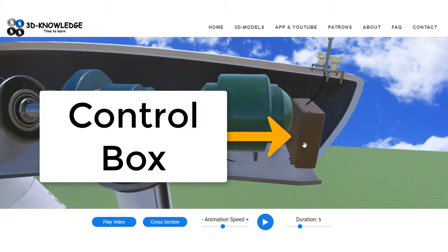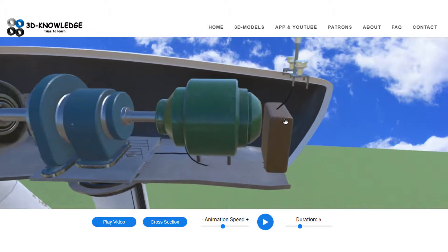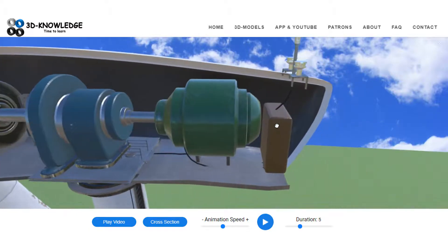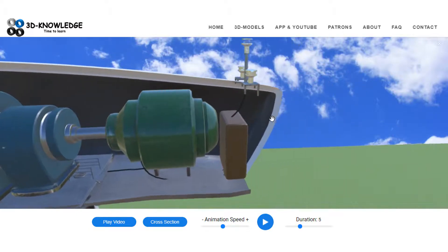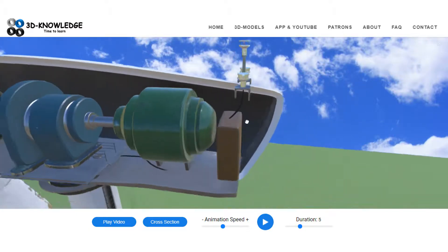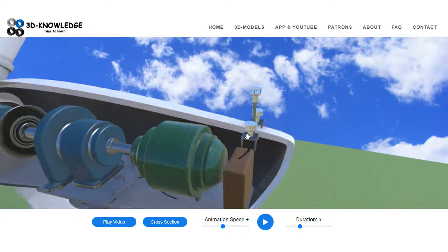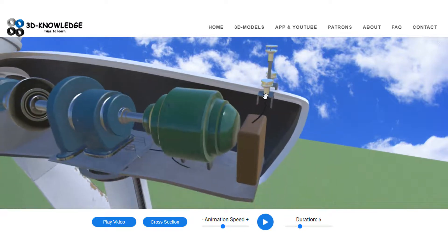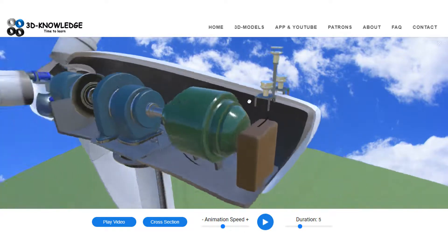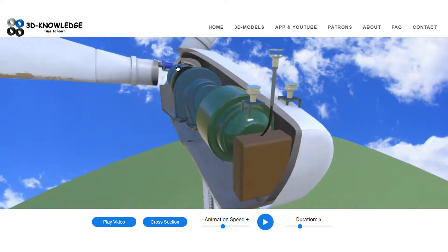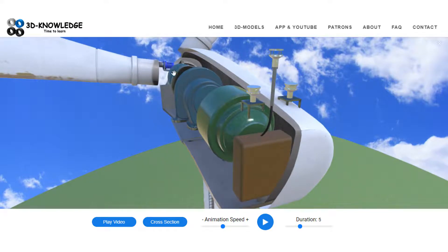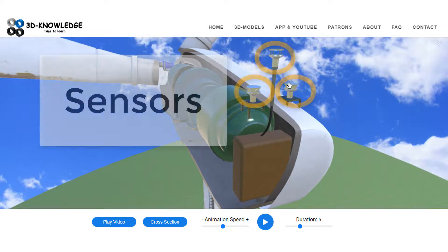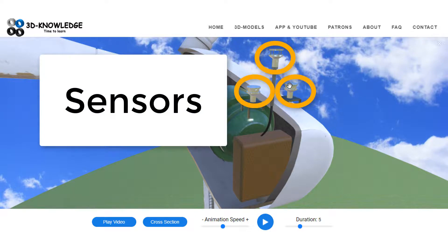We have a control box in the back—that's this brown item—and the control box is used along with the sensors on the top. We can see they're connected by a cable here to turn the entire nacelle, the whole wind turbine, into the wind. So these sensors, one, two, three, they're going to be used to measure the speed of the wind and its direction in order that the turbine can turn into the wind.